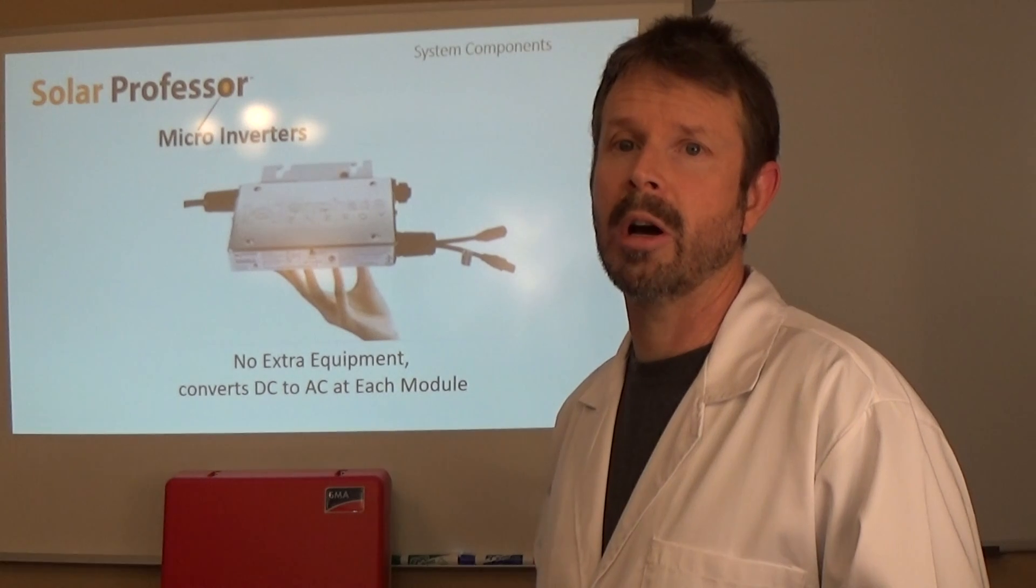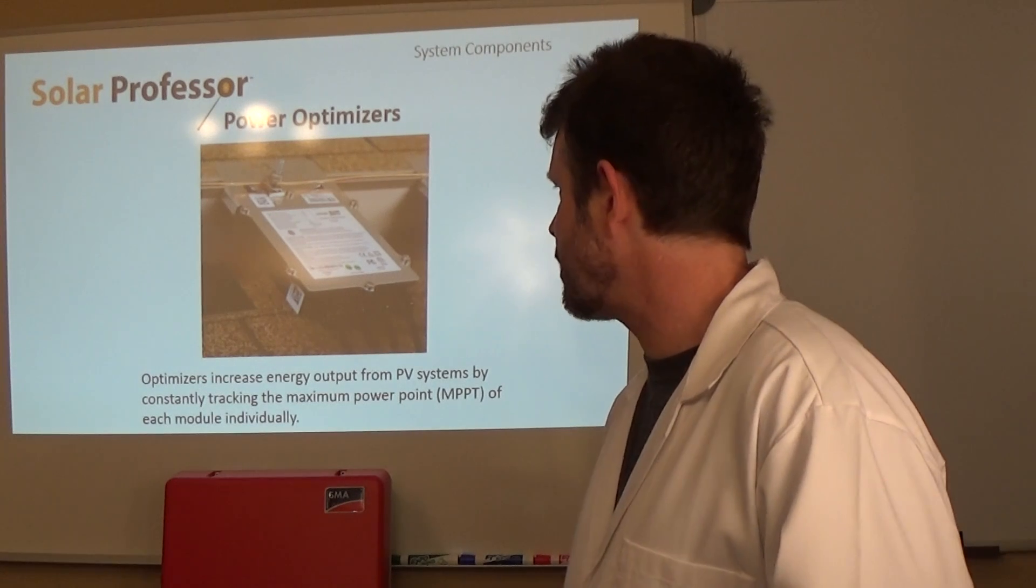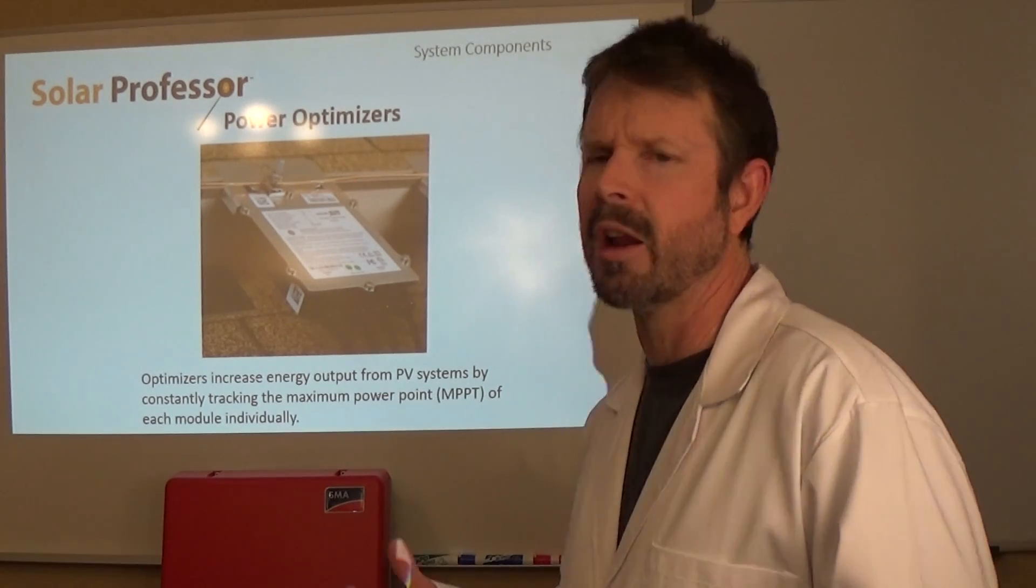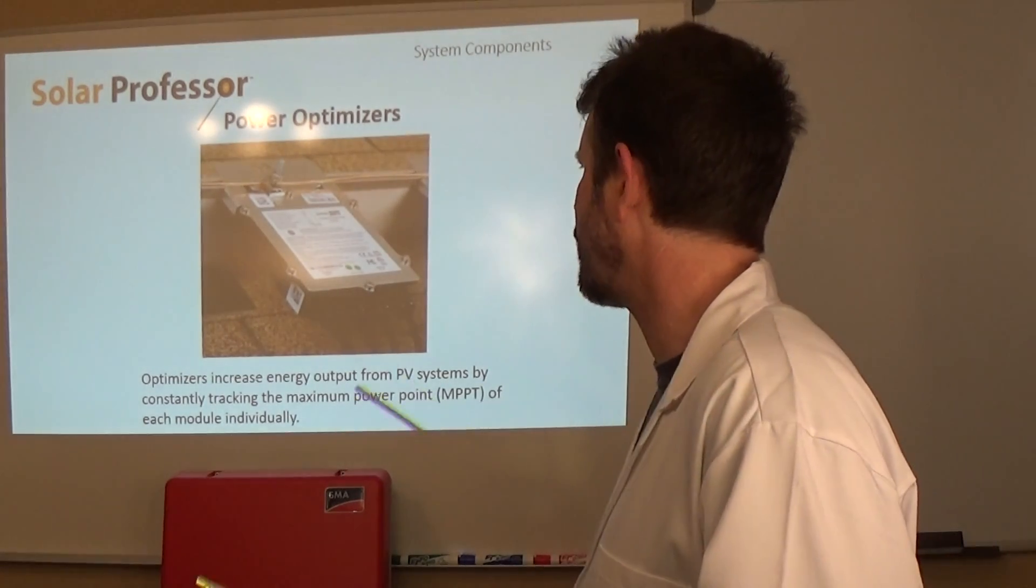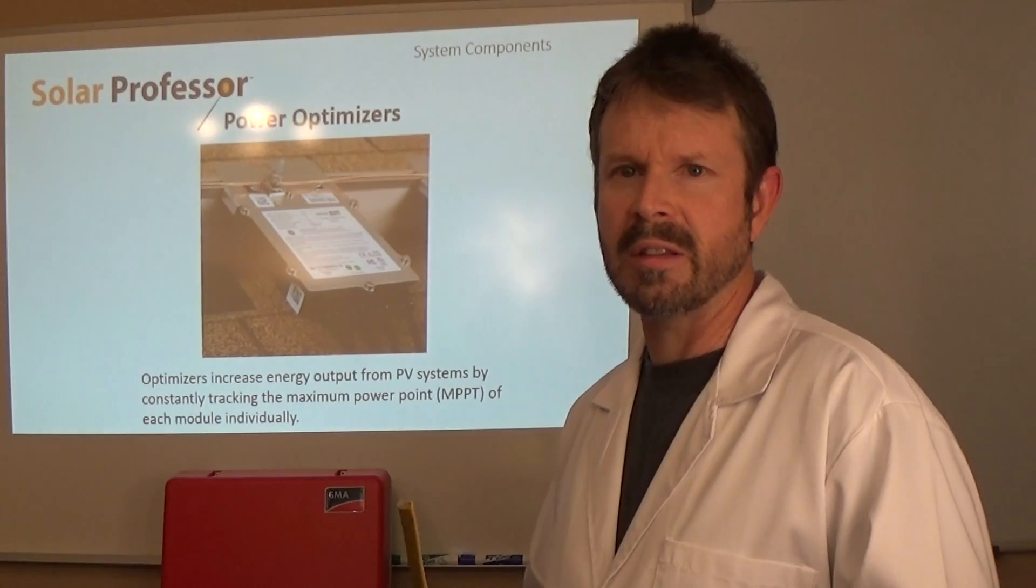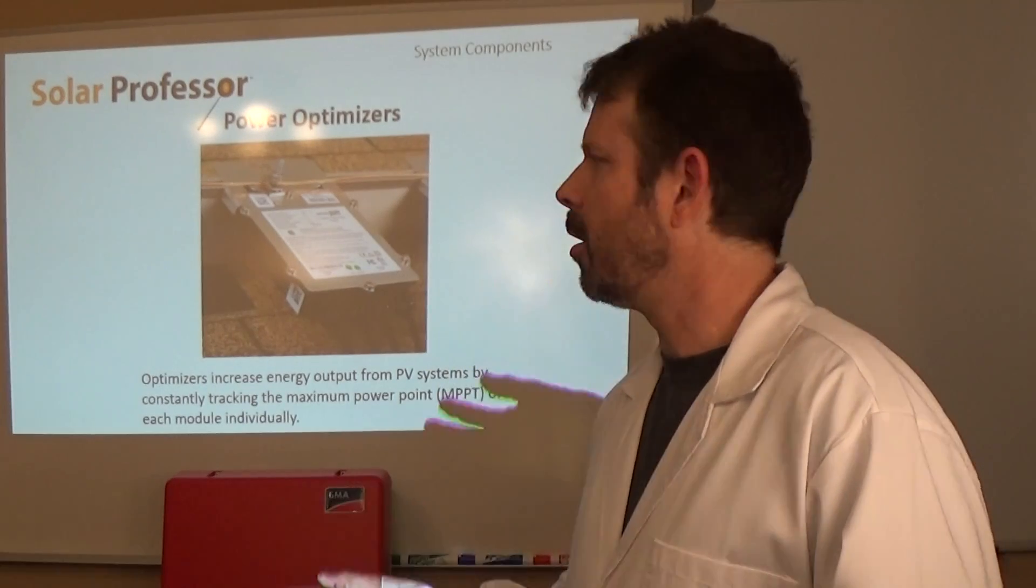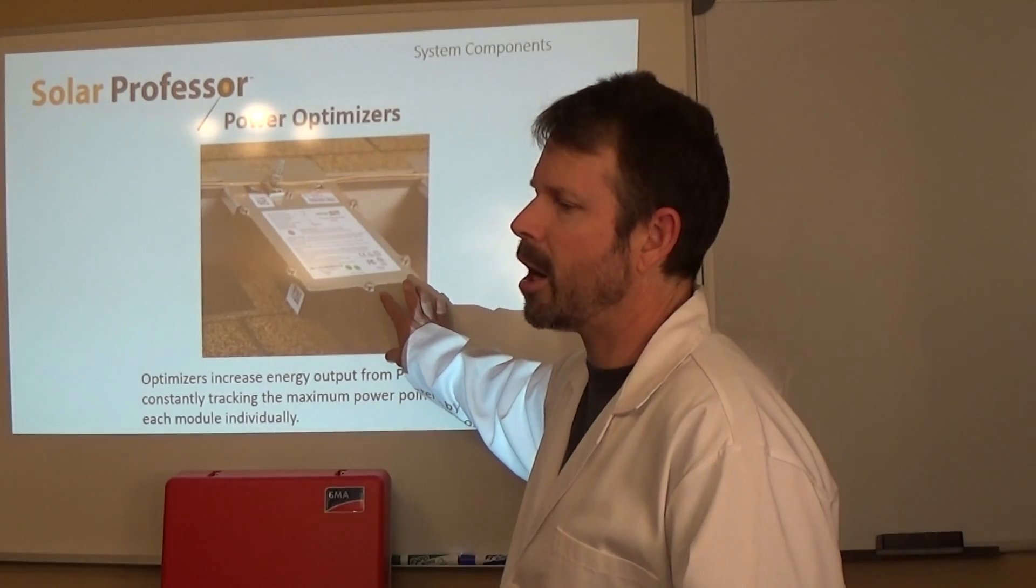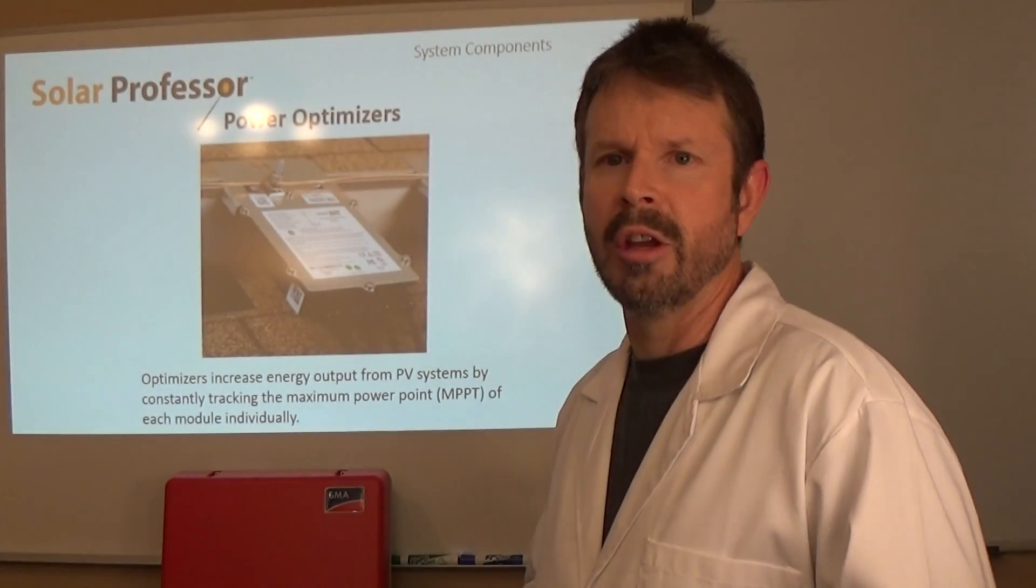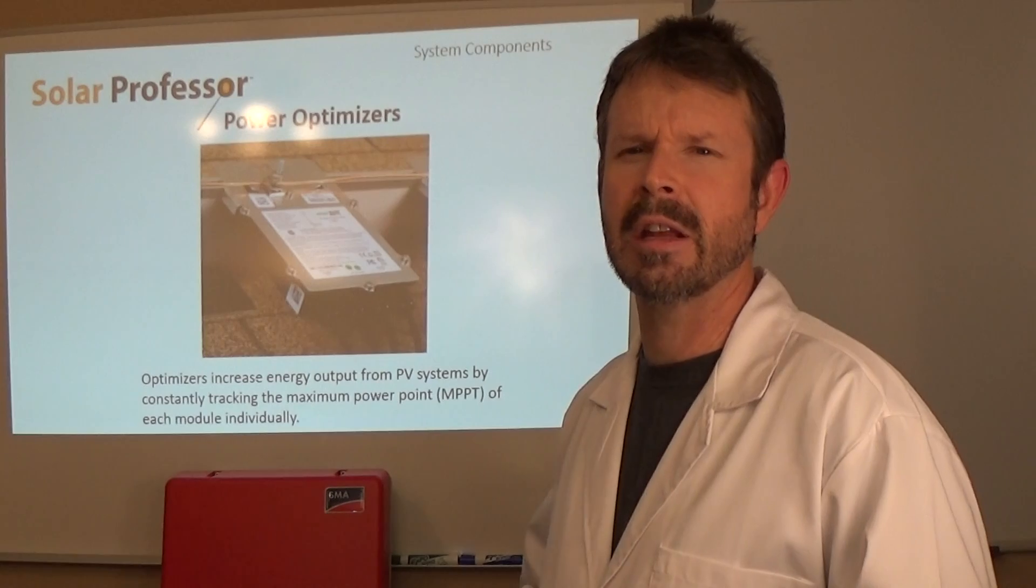Here's power optimizers, they increase energy output from PV systems by constantly tracking the maximum power point. In fact really all modern inverters are going to provide MPPT. A power optimizer is very similar to a micro inverter in that you have to have one per solar panel on the roof. There's less components in a power optimizer and power optimizers keep the current as direct current off of the roof, it's not alternating current off the roof. That's an interesting difference, that's why you have to have the inverter box as well.